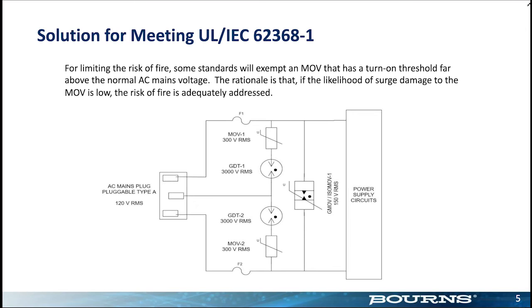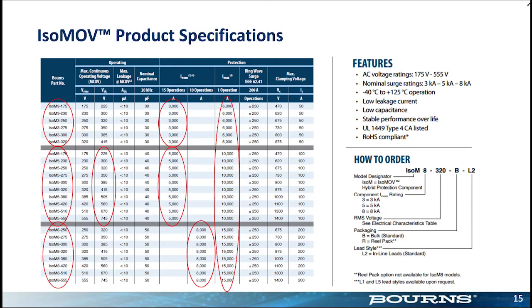All right, so another question we have here is, if the surge is only 1.2 kilovolts, there will be no protection at all since the GDT will not trigger, right? Again, it depends on the component that you select. So I think on the data sheet we do specify the breakdown voltage of that component. So yeah, if you pick one that has a very high breakdown voltage, then it probably will still let through the 1.2 kV. So again, you have to know which is the right component to select, and we can help with that as well if you contact one of our FAE or sales.